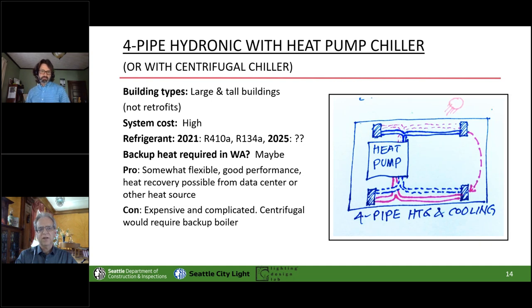Now, notice that at the top I say not for retrofits. You got four pipes. They're not all that big necessarily, but they're each heavily insulated. So finding four big spaces for those four pipes to go everywhere in the building is expensive and really needs space management with it. You also have that local DOAS. You got to bring your ventilation air in separately, and you're going to have whatever that terminal equipment is, fan coils all the way up to chilled beams and radiant slab. That's all space taking and hard to retrofit into existing buildings.